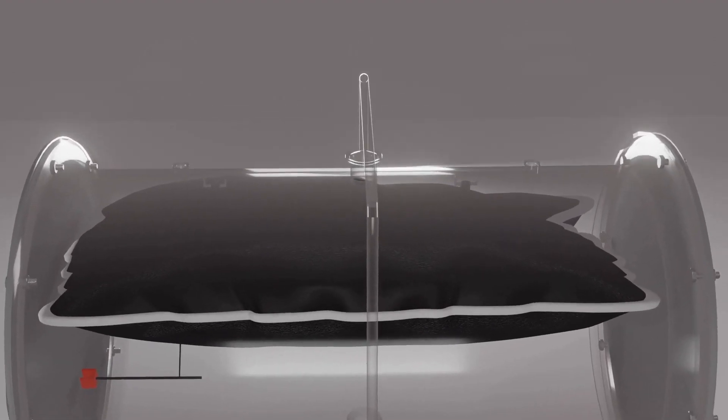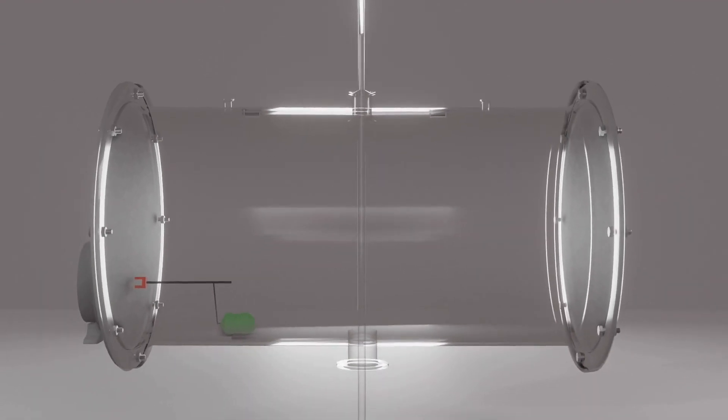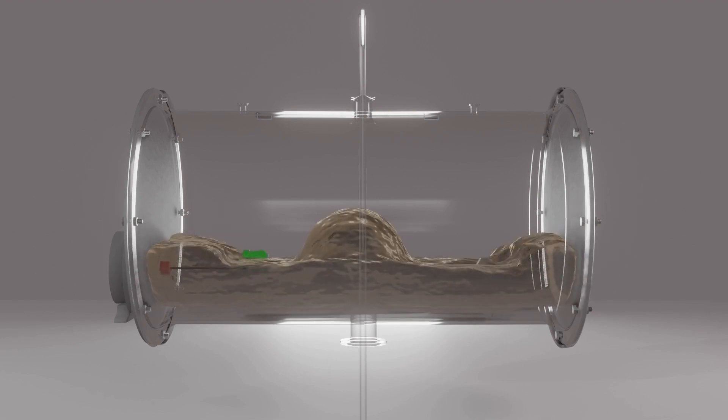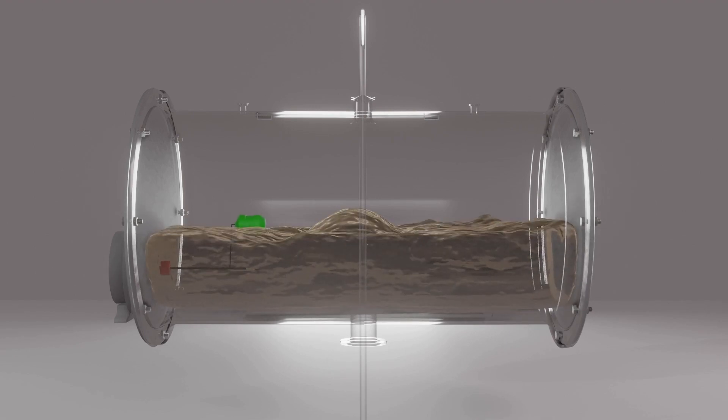Let's first start with why air cells are required in transformer conservator tanks. In the past, air cells were not given in conservator tanks. At that time, 50% of the space was reserved for oil and the remaining 50% was kept empty, in which air is present.